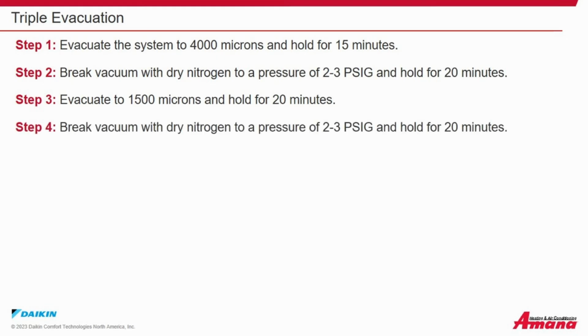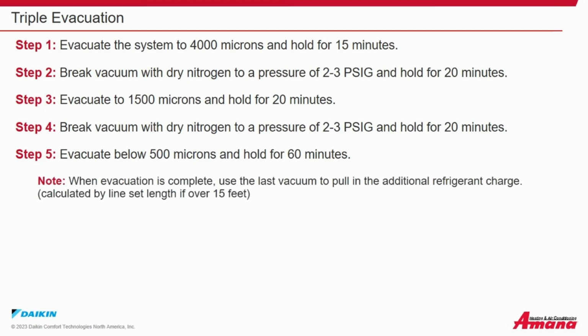Step 4. Break the vacuum with dry nitrogen to a pressure of 2 to 3 psig and hold for 20 minutes. Step 5. Evacuate below 500 microns and hold the vacuum for a minimum of 60 minutes. Note, when the evacuation is complete, use the last vacuum to pull in the additional refrigerant charge, calculated by line length if the line set is over 15 feet.